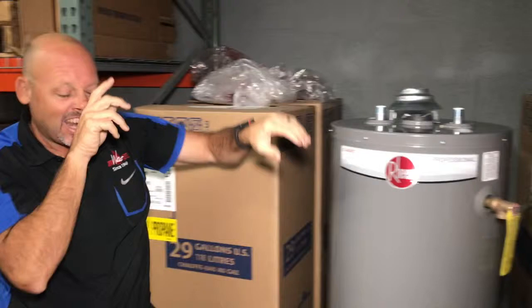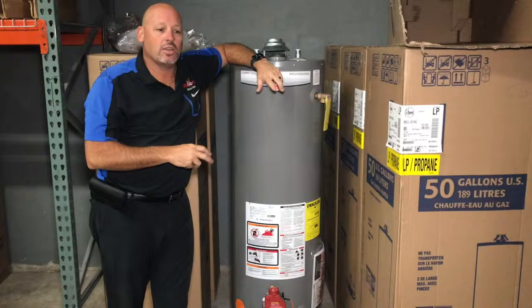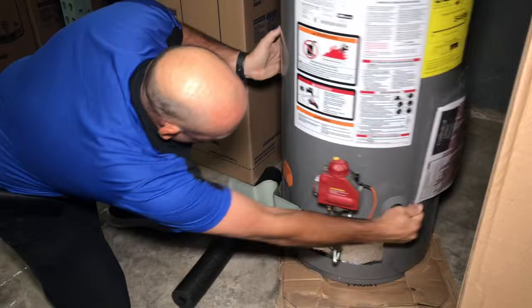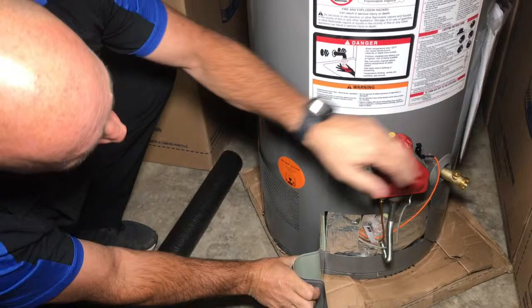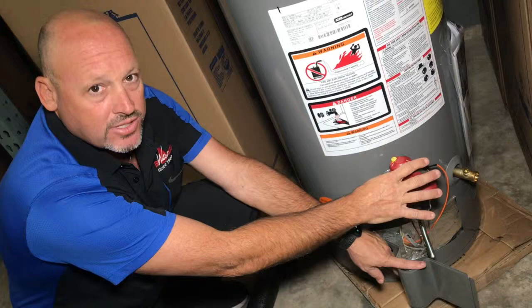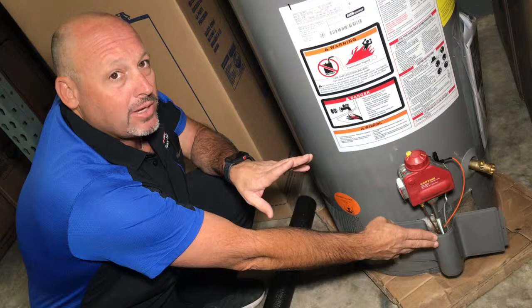A lot of times we get calls that the gas valve is no good, and you can get the pilot to turn on but the heater won't work. As you can see, on the side of this heater it's all vented on both sides, all the way almost to the back. You have the gas valve. If you can turn the pilot on and the pilot stays on, but as soon as you turn it to on or very hot and try to adjust the temperature the heater turns off, chances are your heater can't breathe properly and your TRD — thermal release device — has gone bad.